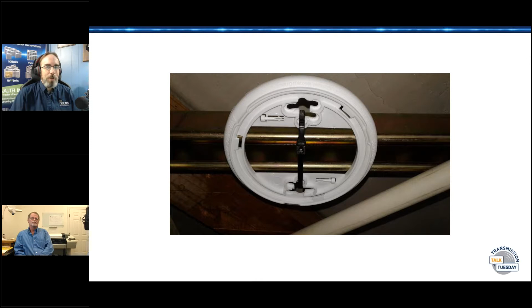Mark mentioned the same thing in the comments, change the battery in your transmitter, and it should be done on a schedule. Whether you do it once a year, or once every 2 years if the transmitter's almost always on, it depends. You'll define the schedule based on your own particular site and circumstances, but you do need to have a schedule. It made me think, I like to label things on the front of the transmitters, when the tube was put in, your TPO, your efficiency. Probably not a bad idea to spend a few more cents on a white label that says battery changed, so the next time you look at the front of that transmitter, you've got a visual reminder that there's a battery in here.